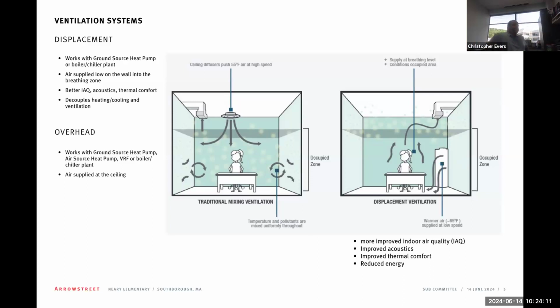There are also products like what's in this diagram, from Price and from others, a product that sits not flush with the wall. It attaches to the wall. They make these prefabricated half rounds and different things. We typically put them where the teaching wall is, because lots of times at lower grades, you would have maybe rugs there. As you go up in other grades, people aren't typically sitting right in front of the teaching wall. And so that's a good place to put them, because you can't put furniture there. That's one thing you don't want. You want to make sure people aren't putting furniture in front of this. That's usually where we put them in classrooms. There would still be some spaces that wouldn't have displacement, say like offices and admin areas. Those would have overhead.